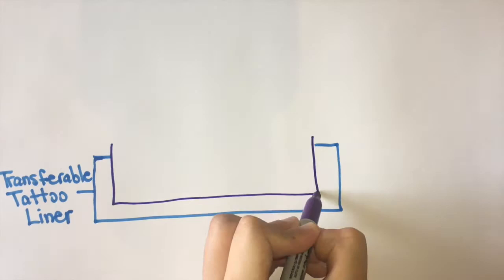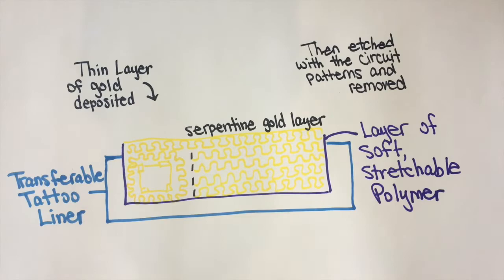Beneath the transferable paper and stretchy polymer layers, the electrode is made of a conductive metal like gold that can pick up electric potentials within our body through contact with the conductive skin surface and convert them to electron currents that appear on the medical monitor.